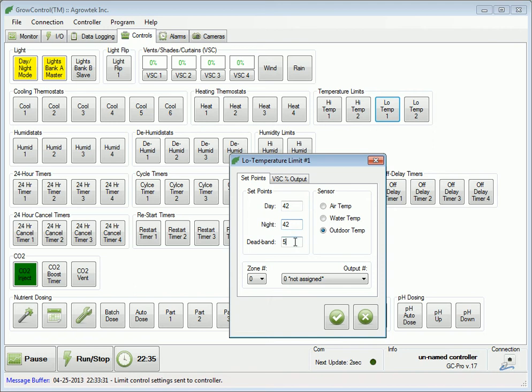Adjust the dead band if desired. In this example, this limit thermostat will be activated at 42 degrees and will be released when it rises by 2 degrees.